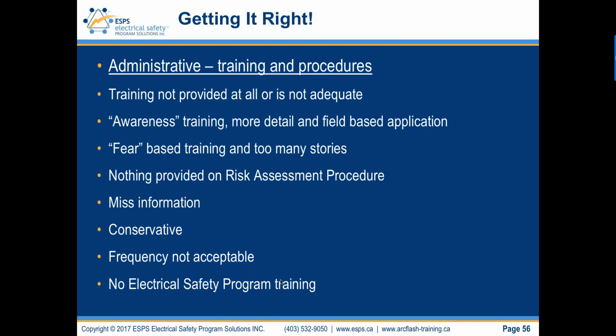That has been the challenge since 2005 in Canada. Training arrived with no practices, no programs. Companies blindly sent their workers on this training, and then nothing came out of it. Nothing, because there was no substantial benefit to the training when the worker came back, because there were no defined policies and practices documented in an electrical safety program. So we need more detailed training, and we need field-based application as the approach. No more what the clauses and articles are, but telling the workers how to use that information in the field, how you'd actually use it to get the benefit of residual risk reduction, right?